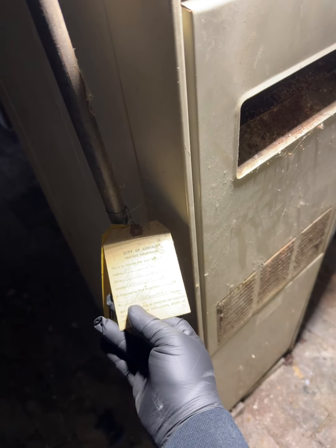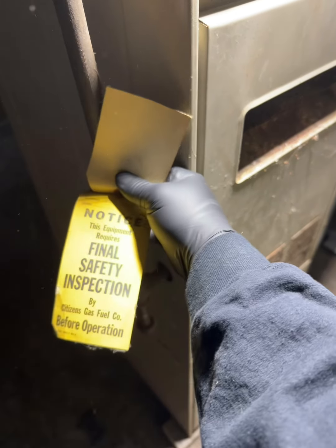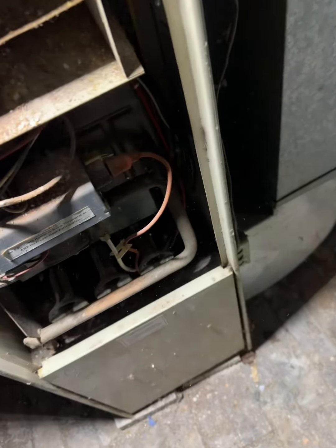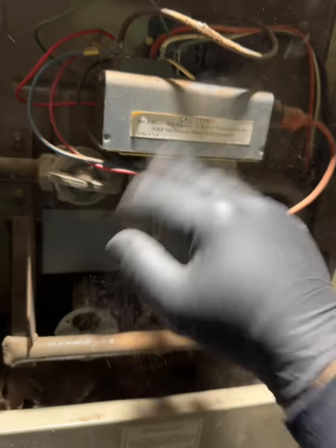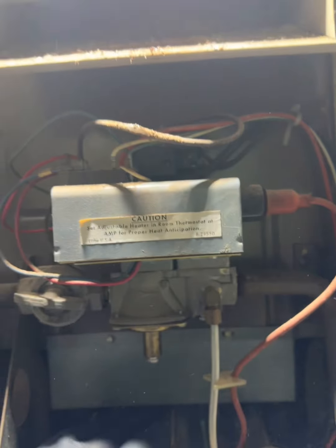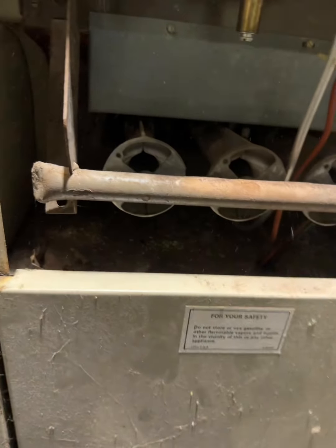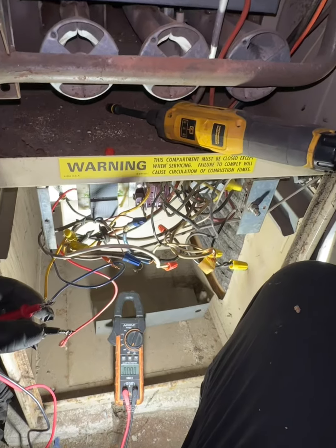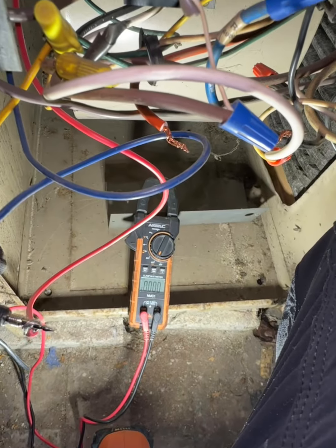Filters look like... All right. Got an old Lennox here. She's old. She's got the old gas valve on it. Oh, man. Oh, brother. So it should light itself. Okay, let's bypass the thermostat real quick. That's thermostat, nothing. We want to make sure there's voltage going to the unit. There is 120 volts. Coming out of the transformer, we have nothing. We have nothing here. So that transformer's bad.